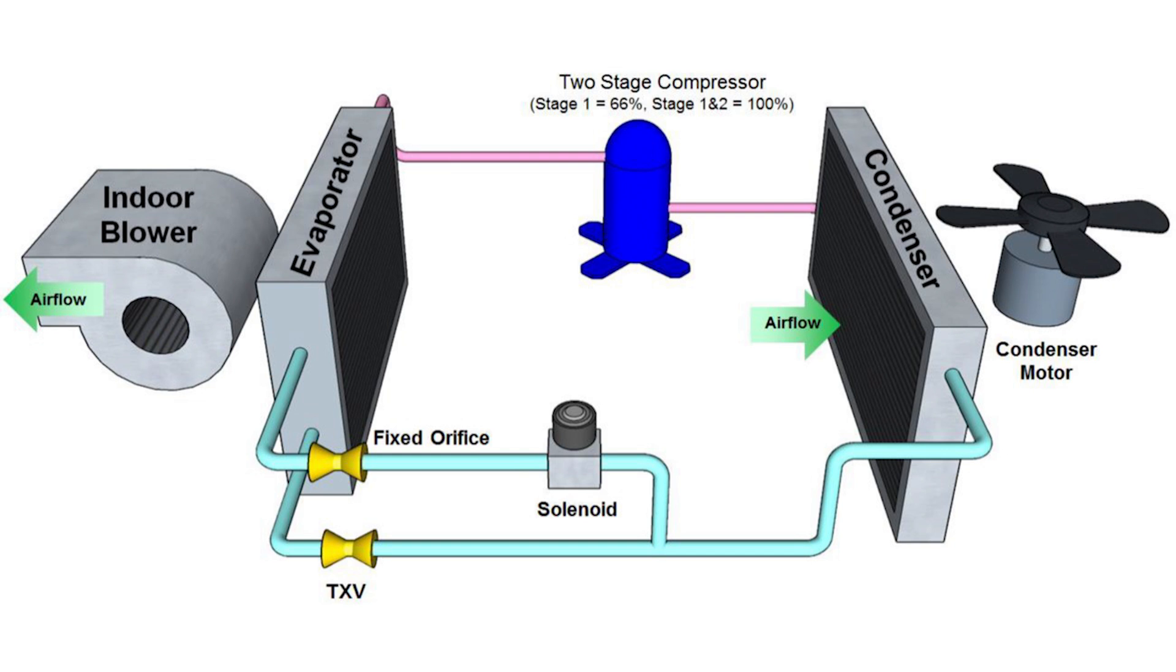When it comes into the evaporator coil, we're going to actually have that split. So stage one will go to the TXV, which will modulate just like it normally would, and that will go to the evaporator. But then stage two of the compressor will open up a solenoid valve, which will allow refrigerant to flow into the rest of the evaporator as well.